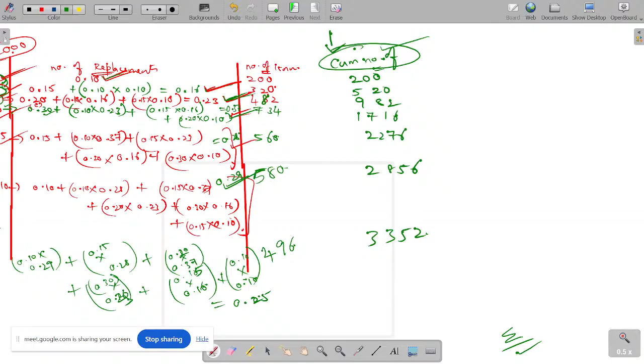So the number of periods is 1, 2, 3, 4, 5, 6. Actually, there are 6, but we have calculated 7 also. Then the cumulative values here are 200, 520, 982, 1716, 2276, 2856, and 3352. This I'm copying from the earlier table. Now we'll go for breakdown maintenance. Breakdown maintenance means whenever it occurs, we replace it. So with the help of this value, we'll go for the monthly breakdown value. It's 200 transistors. For one transistor, it's 30 rupees. So 200 into 30, 6,000.